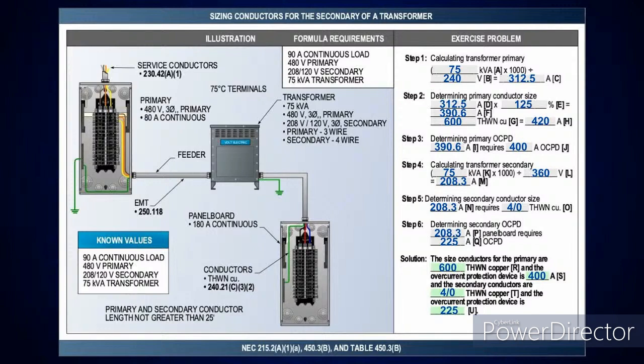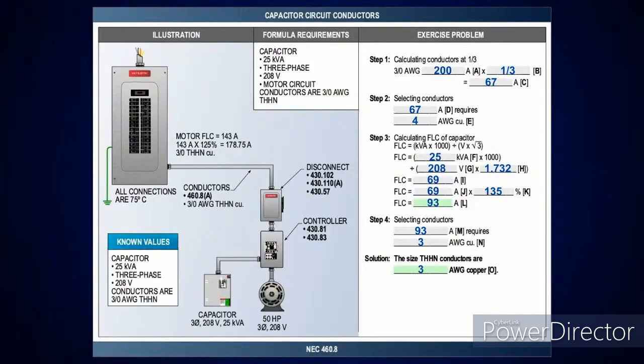I'd need a 225 amp overcurrent device. Right. Okay. So that's how we go about sizing that. And you have to be careful too in that instance because not always do you need a primary and secondary overcurrent device. No, you don't. All that is showing you how to do the conductors and how those conductors dictate the size of that overcurrent device.